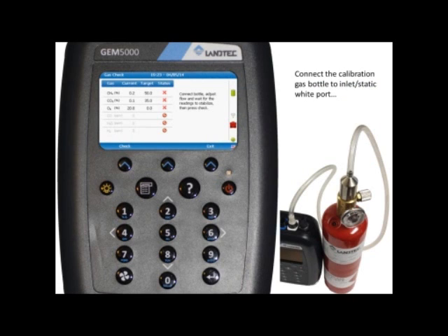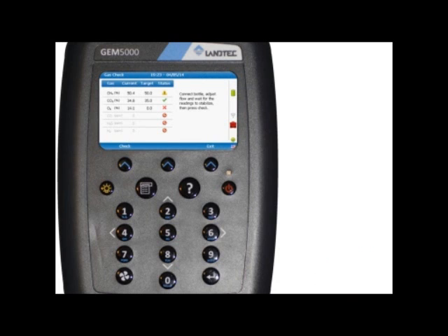In the gas check screen for the CH4 high mix, at this point, connect the regulator hose to the inlet or static port on the analyzer, which is also indicated by the white color around the port. Open the regulator for the gas to start flowing and wait for the readings to stabilize. Once the values are stable, press the left soft key to select check. This will start the 1-minute timer. Once the 1 minute timer is activated, you're going to see under the status column symbols going back and forth, the current values stabilizing.